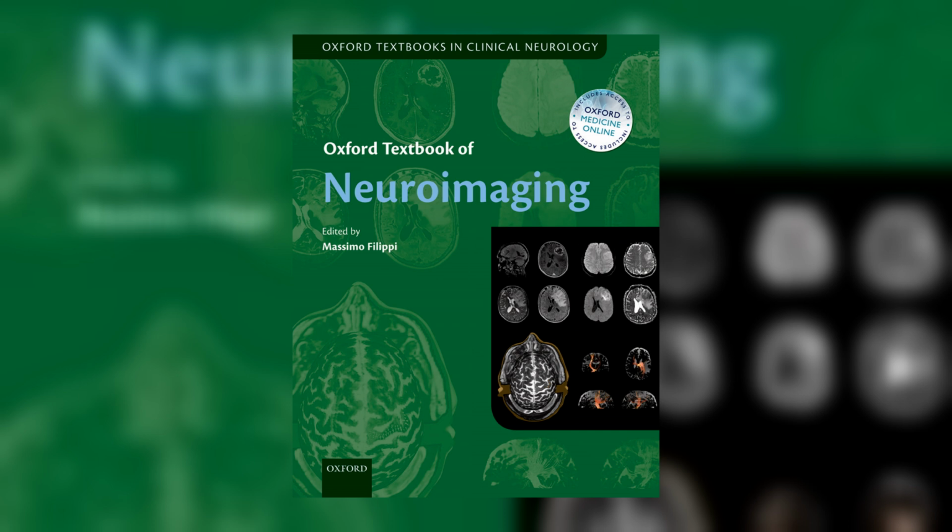This section explains what positron emission tomography really measures and why its numbers live or die on correction. A positron annihilation throws two 511 kilo electron volt photons back to back. Catch both in coincidence and you have drawn a line through the point of emission.